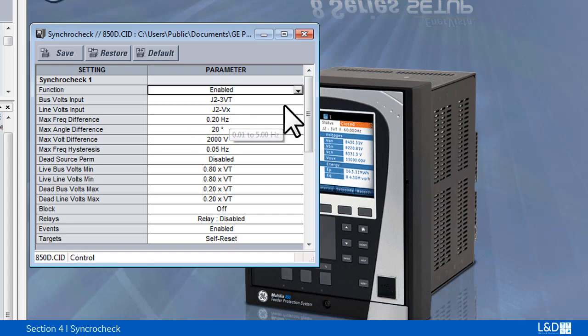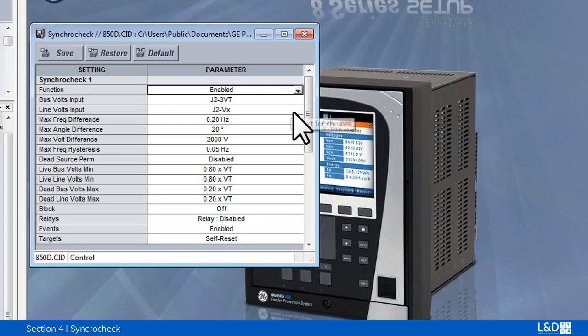By default, three VTs are used for bus voltage input and auxiliary VX is used for the line voltage input. Depending on the order code, both line and bus sides VT can be three-phase VT. Then the VT types must match.